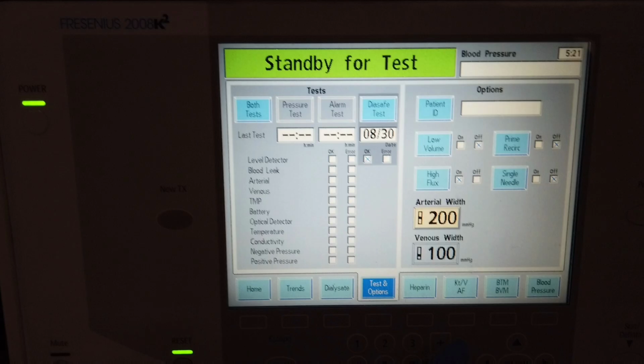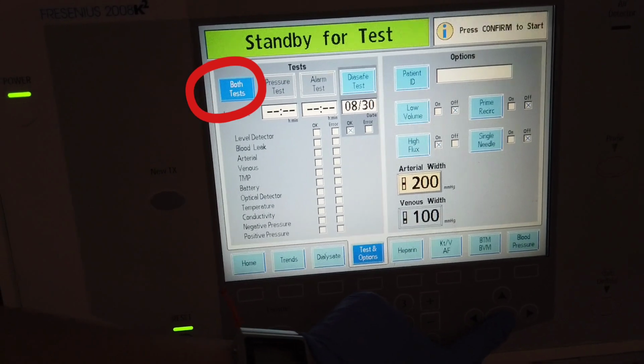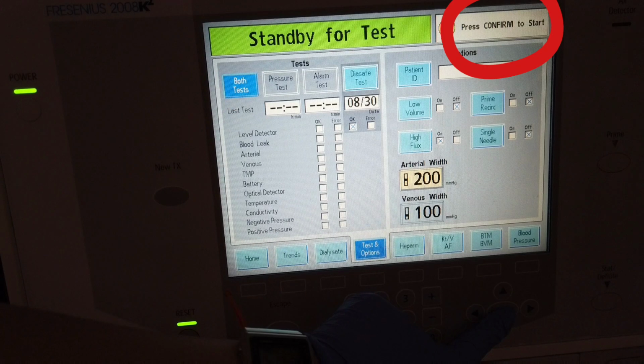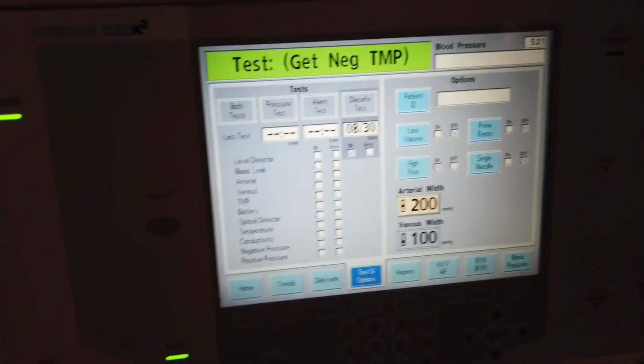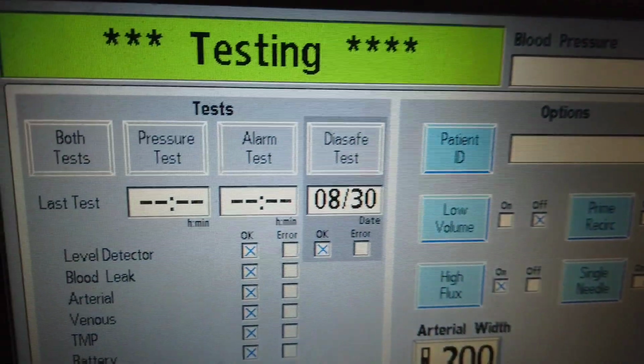Typically, when you flawlessly prime the whole setup, the machine itself will automatically show this standby for test message. You can let it test automatically, which will take a few minutes to start, or you do it yourself by clicking the Test and Options button, then choose both tests, which then instructs you to press Confirm to start. If the testing message is in red instead of green, most likely the test will fail. Observe the air detector clamp here is open. The venous line can actually be threaded within it without affecting the testing. So is the arterial transducer line, which I forgot to attach, that should be done before testing. This is how the screen looks like when the test is complete.